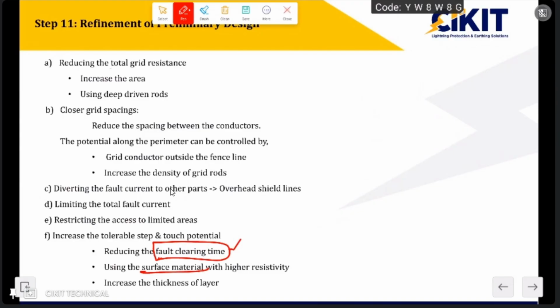So I have shown one table which explains the resistivity for different materials that are commonly used as a surface material. Initially, if I'm using gravel, and I find that the design cannot be met, then I can change the material from gravel to concrete, or I can change from gravel to asphalt. If I increase this value, then the tolerable value will increase. And another option is increasing the thickness of the layer. If I increase the thickness of the layer, then the overall resistance will increase. Because of this increase in overall resistance, the tolerable step voltage and touch voltage will also increase. So by using these three values, we can increase the tolerable limit.